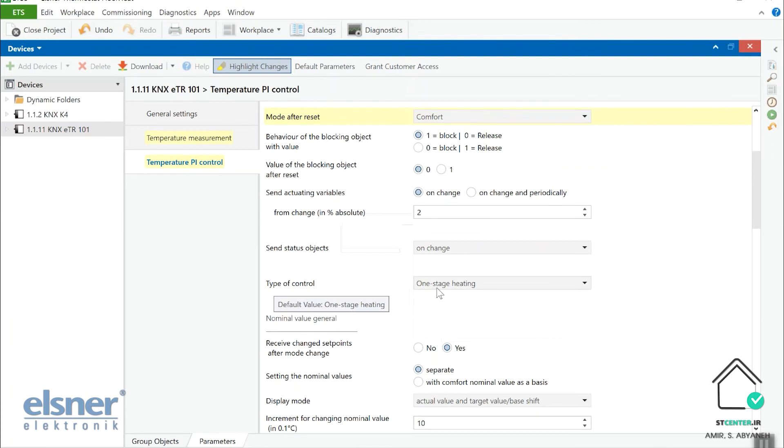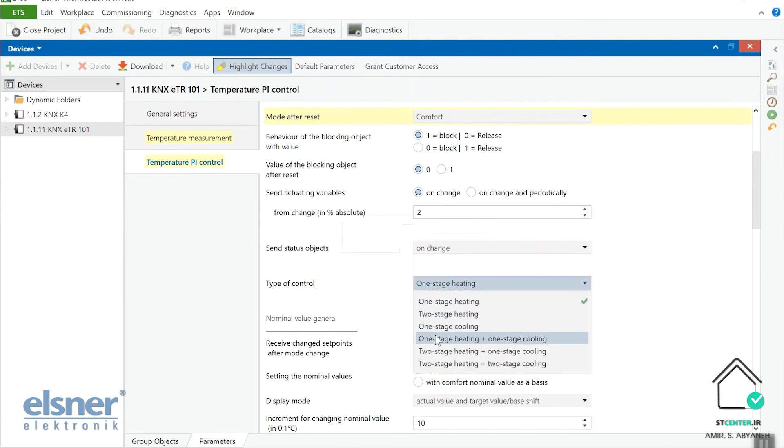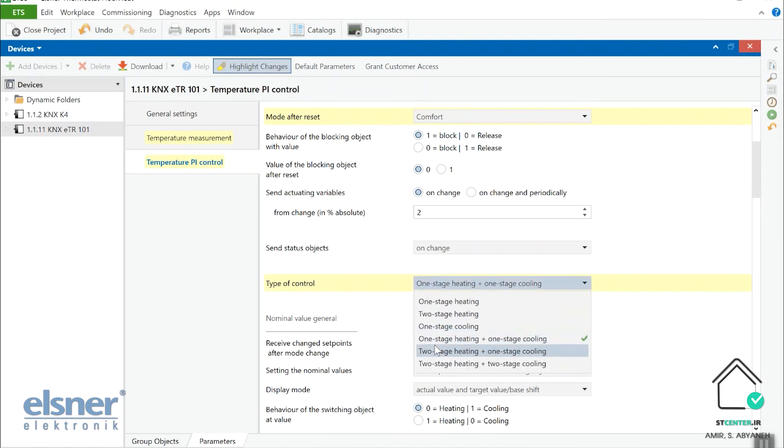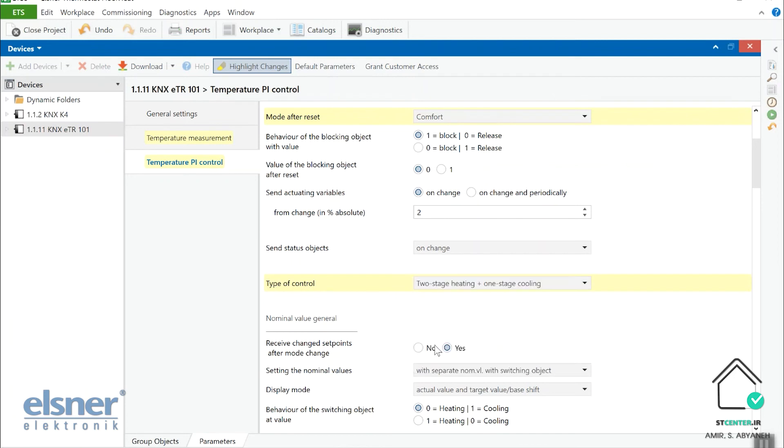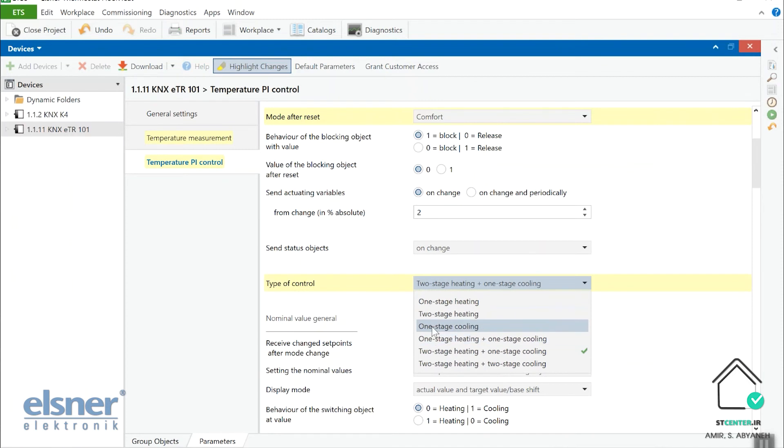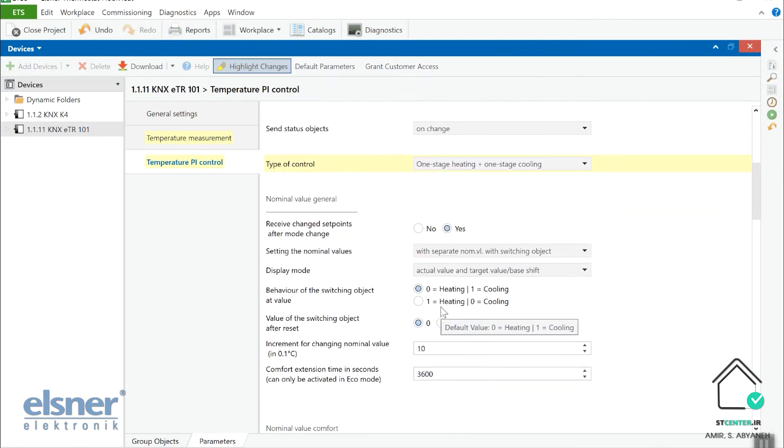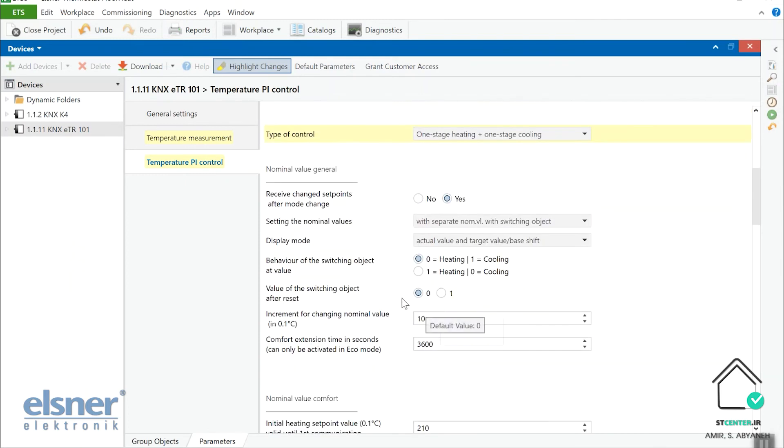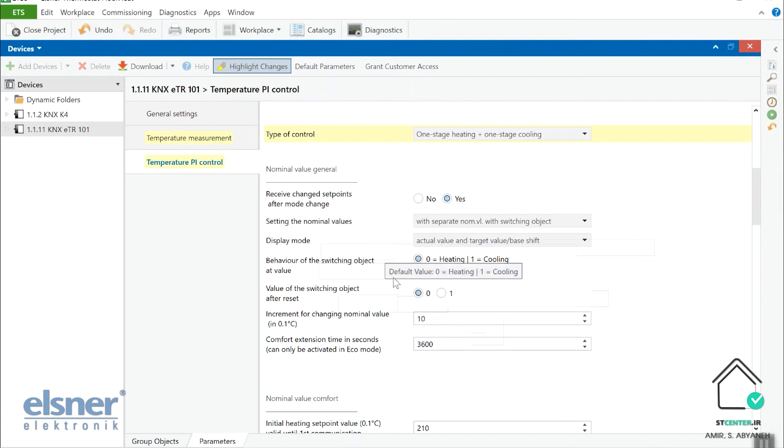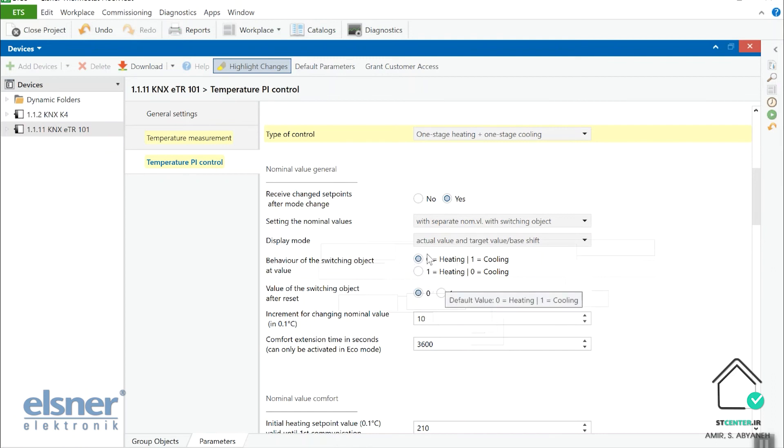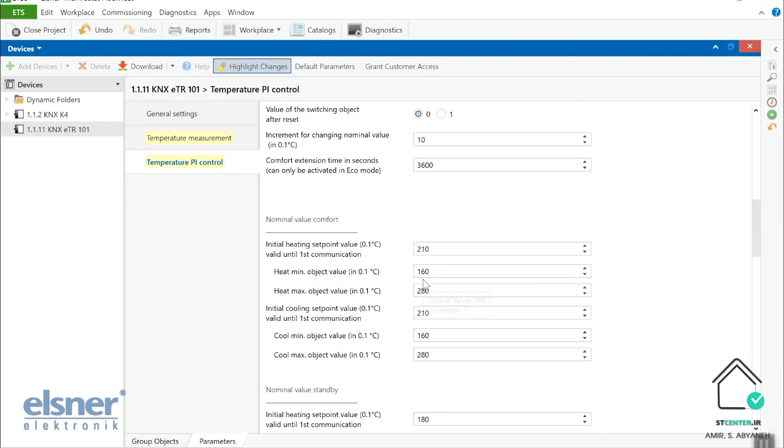The important parameter here is type of control. Are you going to control one stage heating like floor heating, or one stage heating and one stage cooling like the fan coil units, or for example two stage heating one stage cooling, for example some additional heat and cool to what you have regular in a room. So if you for example put it in one stage heating one stage cooling then you can see how you are going to control. First of all, there is an option to tell the system how to behave to change between the season. For heat and cooling there is opportunity to configure this product with most of the brand mechanics because it makes you flexible here. This is nice.